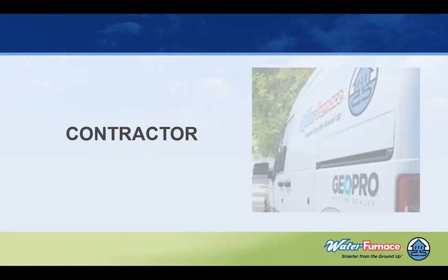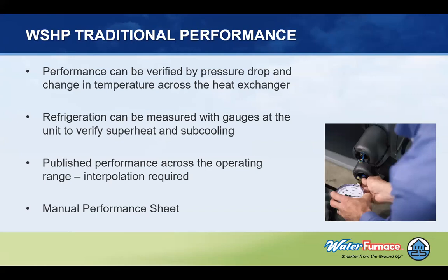So next, we'll move on to what do you get as a contractor? Just as a reminder, water source heat pumps, geothermal heat pumps, have had a unique characteristic in the market for many years, and that is that you can get the performance of that system as operating right now without any guessing. That happens by just measuring the pressure drop across the heat exchanger and getting the temperatures across the heat exchanger. By doing that, you can use your catalog and compare to the manual to know, based on the pressure drop and the change in temperature, what is the performance of the piece of equipment.